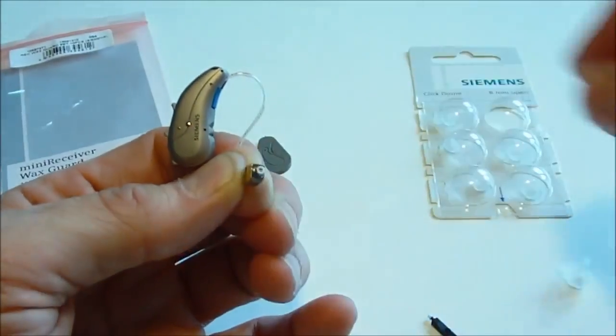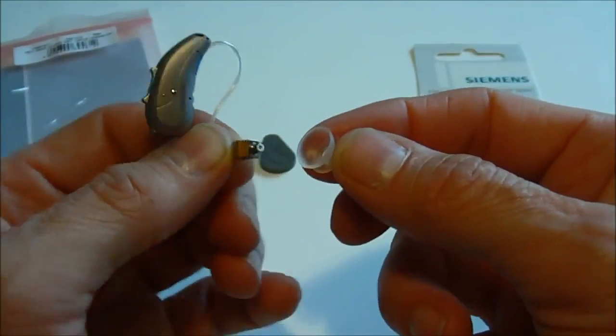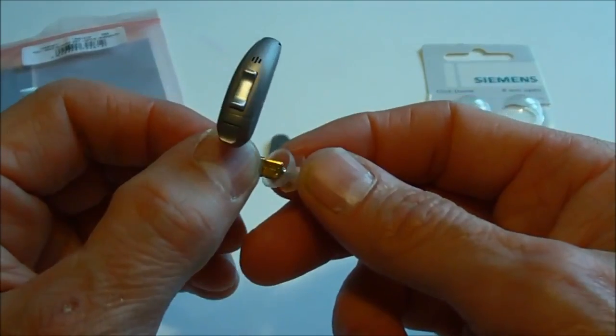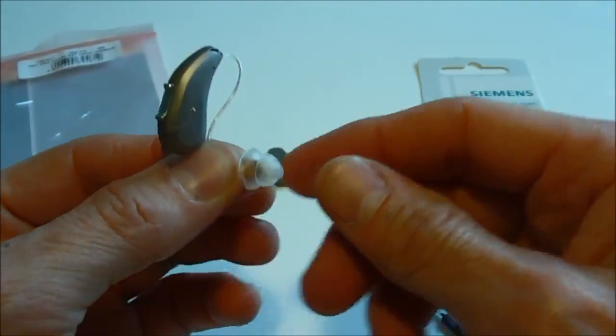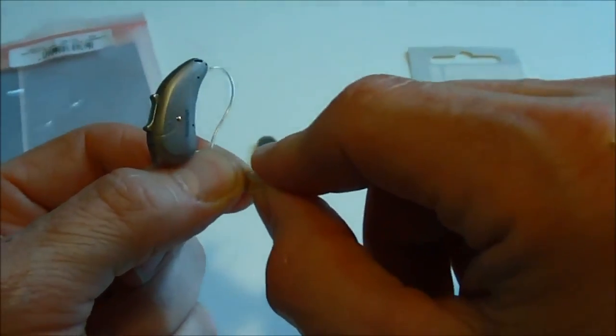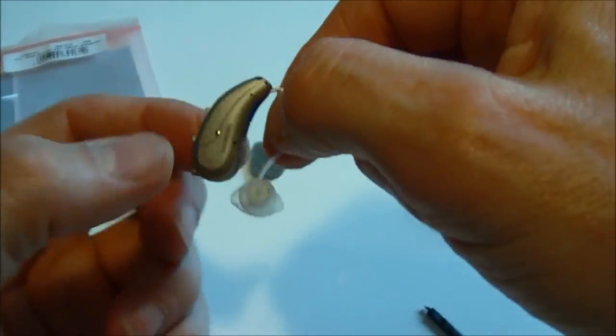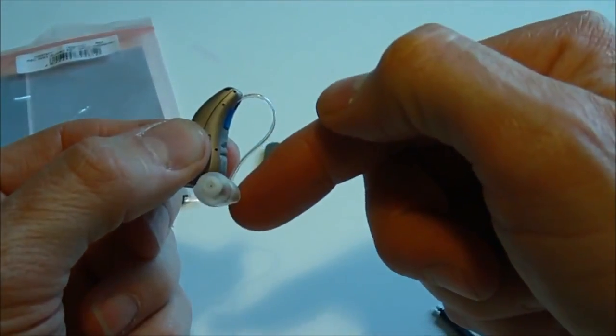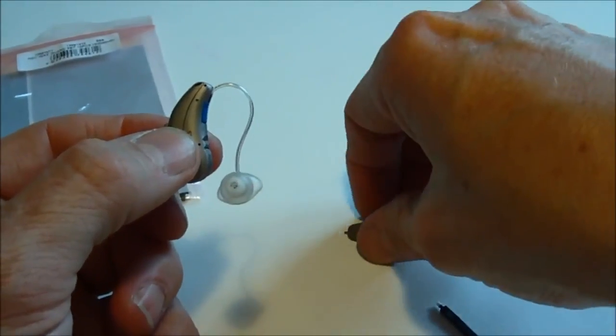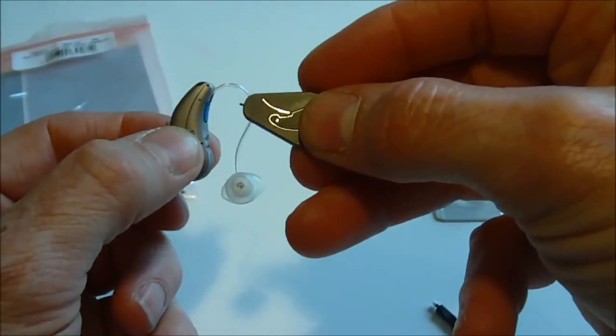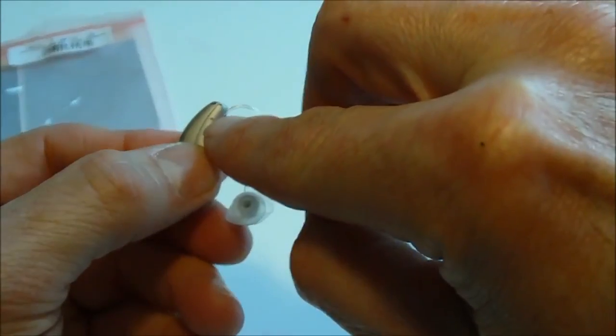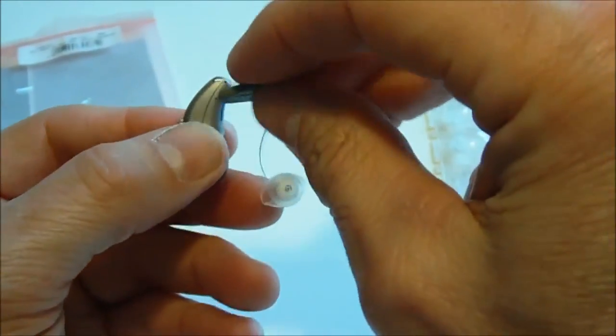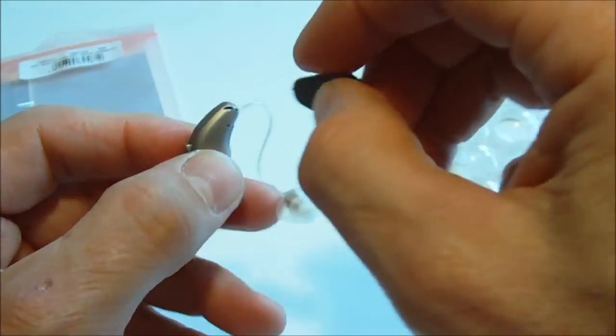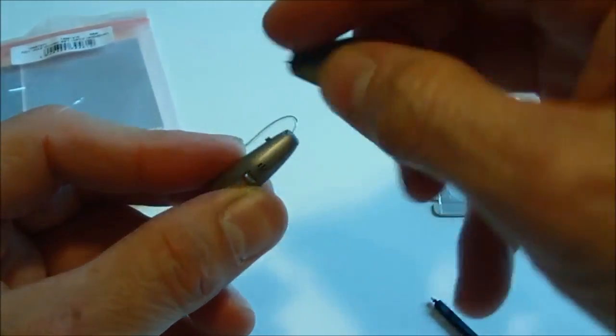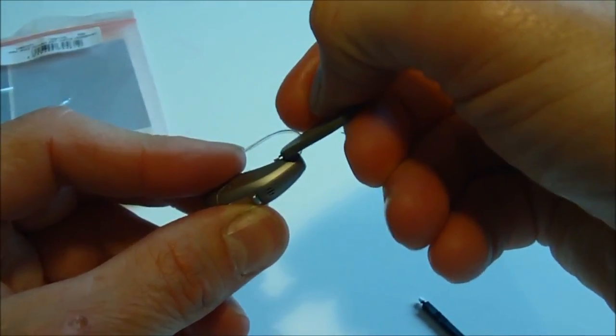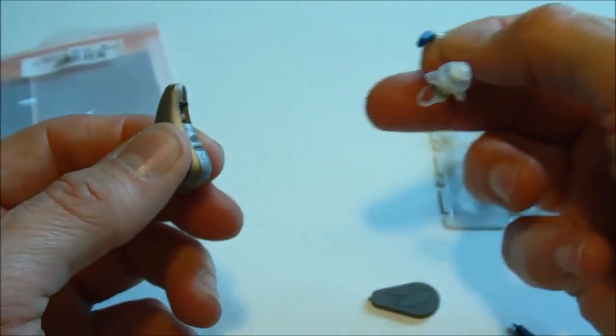I'm going to take this one off, and then we take the tip, line up the end of the speaker wire into the hole and just push until you hear a click. That is now on firmly. If you want to take the speaker wire off, this can be done by using a pin tool. This is the one Siemens supply, but any pin will do. And there's a little hole just by the tab. If you poke that, it goes in, and on the other side it comes out by 1mm, and then you can just take the speaker wire off.